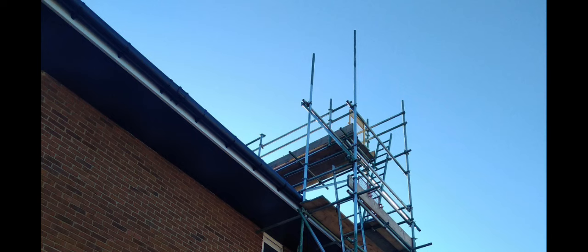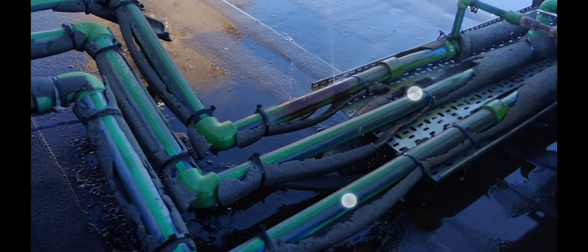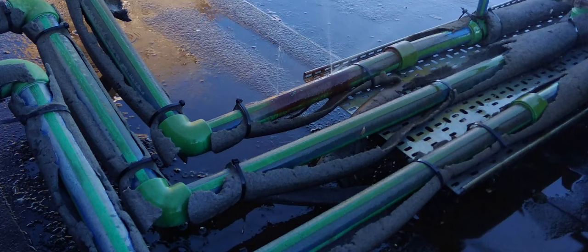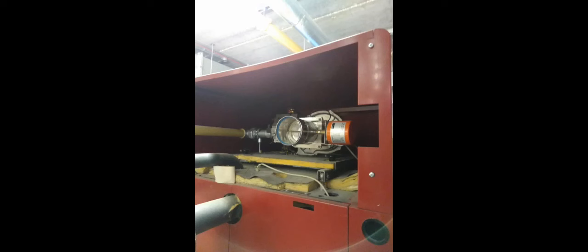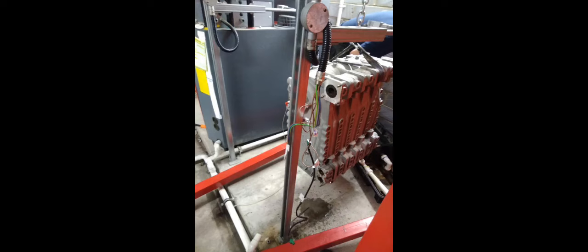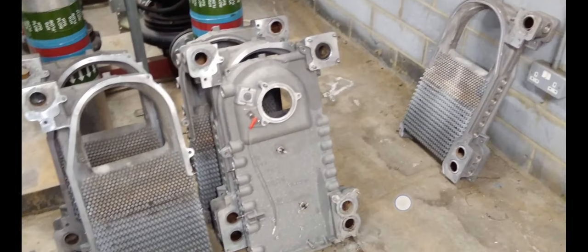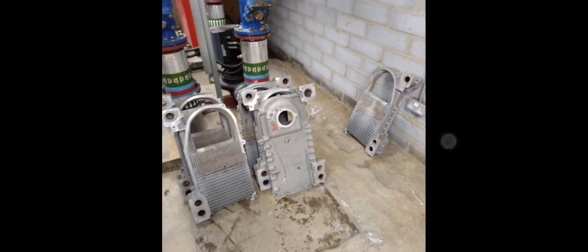These are pictures from inside a Vaillant commercial boiler. On this particular site, scaffolding was put up and we had to change the vertical flues. Remember the damaged flues I showed you earlier? Well, on the Vaillants, we were repairing them. And here they are. In this particular job, we have some leaks on a roof, quite a few pinhole leaks. I recall this particular site, I think I went here maybe in a school, and I was inspecting or having to replace the damper motors. This was probably one of my first experiences with an Ideal Concorde Super Series. What a classic boiler or classic module. In this picture here, the two of us removing sections of a boiler and trying to seal them. Here we have it. And here's the boiler. I reckon it was a Roma.